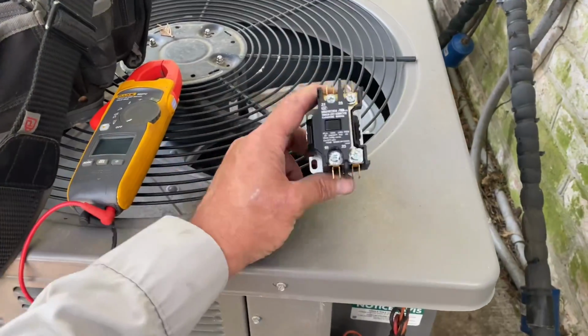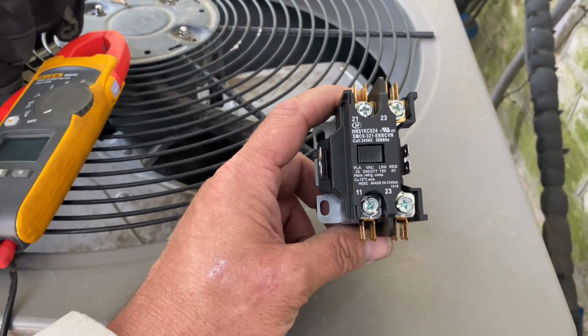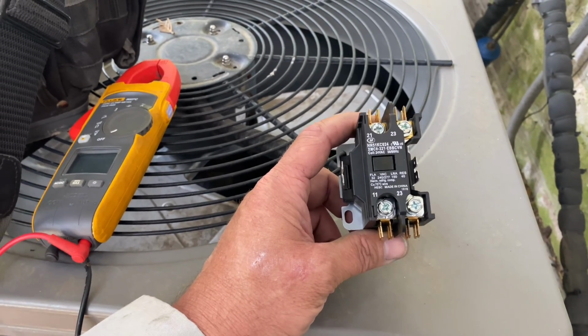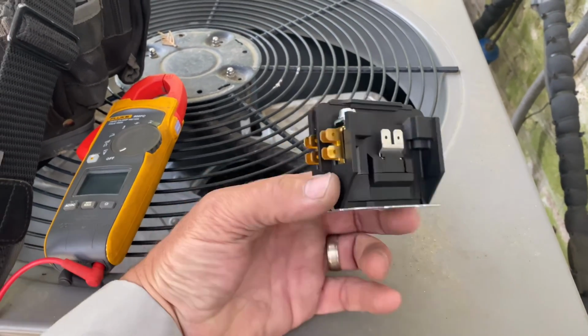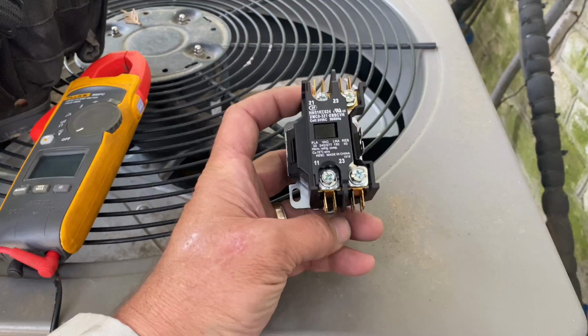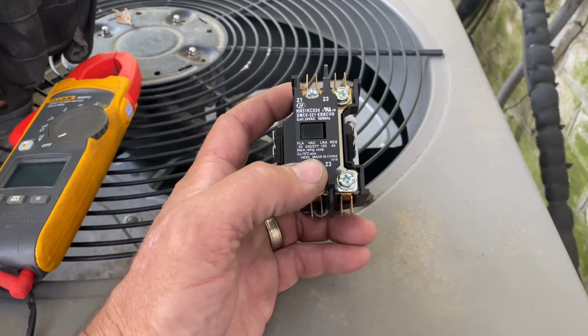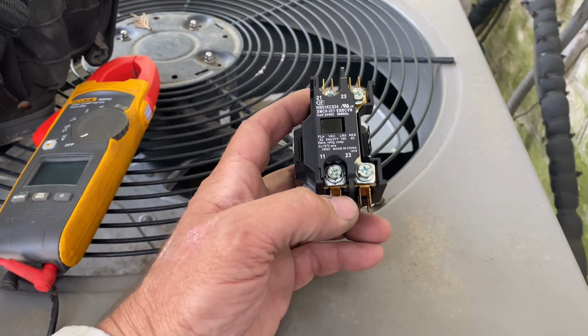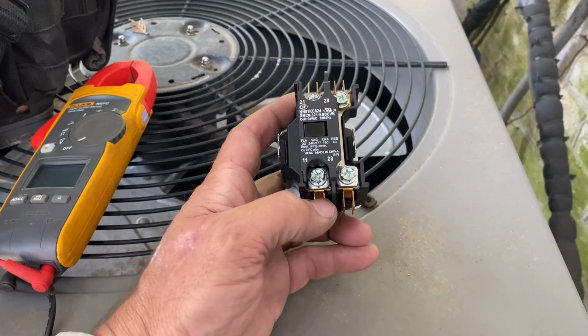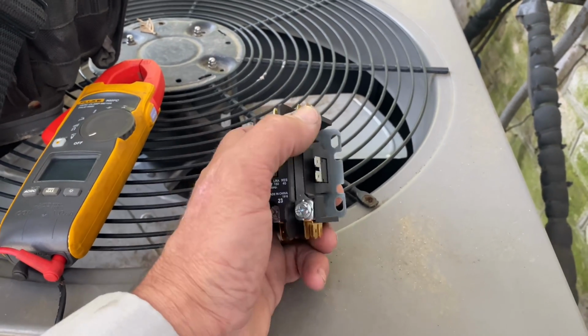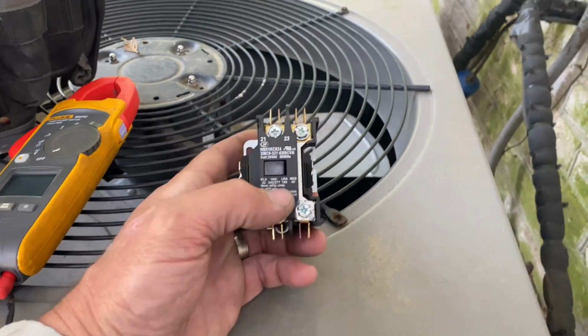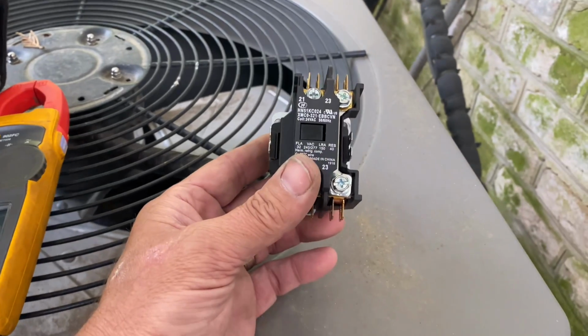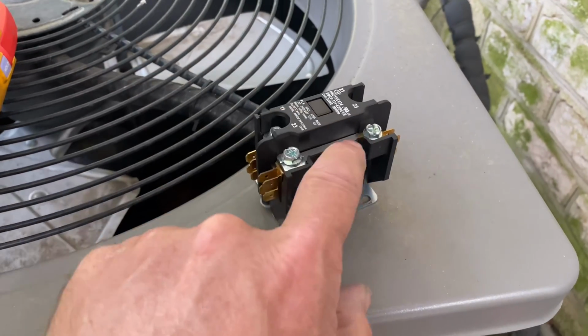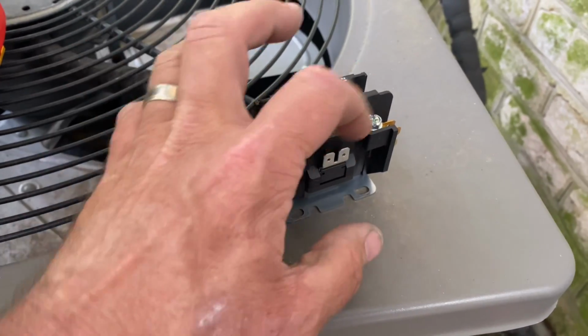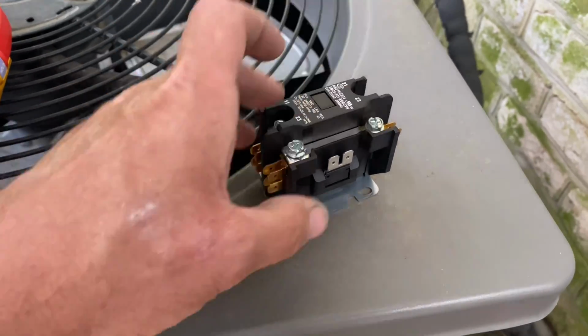All right, so here we are at the outdoor unit, and full disclosure, I already diagnosed the machine. Here is the contactor. Its job is to close a circuit. We have L1, L2, which is line 1 and line 2, T1 and T2, terminal 1, terminal 2. This is a single pole contactor, right? Because there's a shunt here, which is always powered. So if there's power here, there's power there.